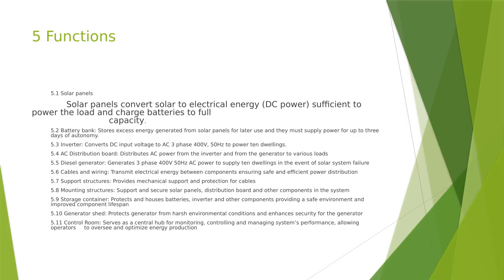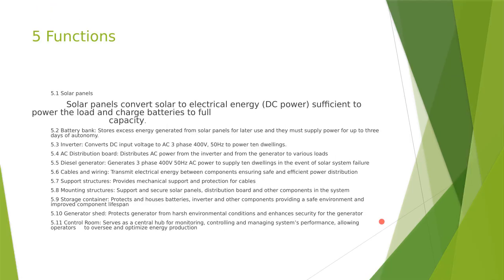Then we move on to the detailed functions of the specified components. We've got solar panels. They convert solar to electrical energy, which is DC power sufficient to power the load and charge the batteries to full capacity. So the battery bank will be storing excess energy generated from solar panels for later use, and they must supply power for up to 3 days of autonomy. Then the inverter converts DC input voltage to AC 3-phase 400 volts 50 hertz to power the 10 dwellings. And the AC DB distributes AC power from the inverter and from the generator to various loads.